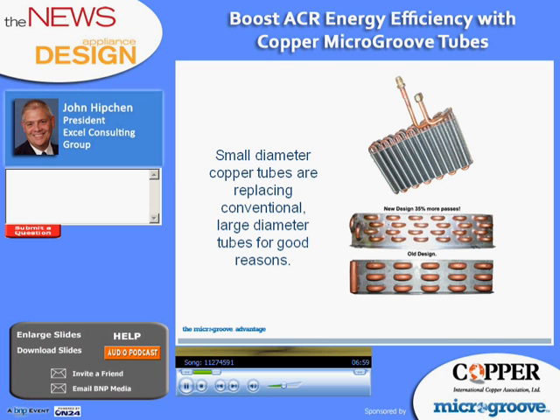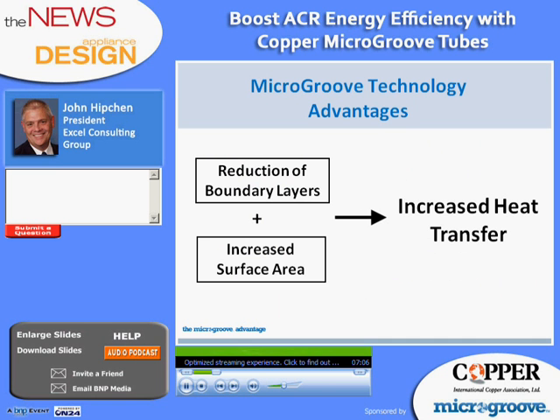So let's look at the advantages of MicroGroove tubes and the technology supporting this trend toward their use. The two main phenomena that contribute technically to the advantages of MicroGroove tubes are number one, reduced boundary layers, and number two, increased surface area. The name MicroGroove refers directly to both of these phenomena. Micro, referring to the small diameter tubes and the increased surface area that results from the small diameters, and groove refers to the internal enhancements inside the tube that reduce boundary layers. Together, both of these lead to dramatic increases in heat transfer.